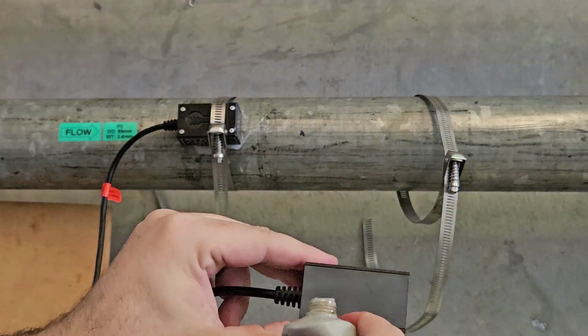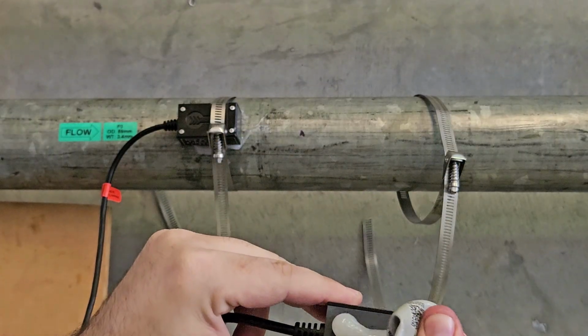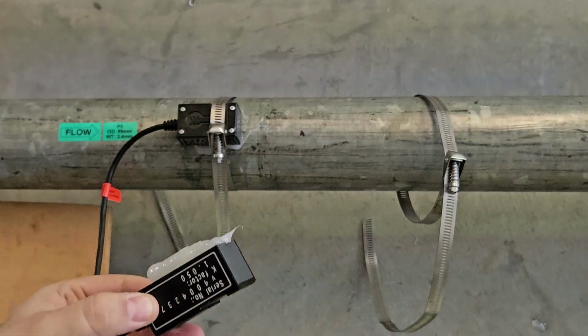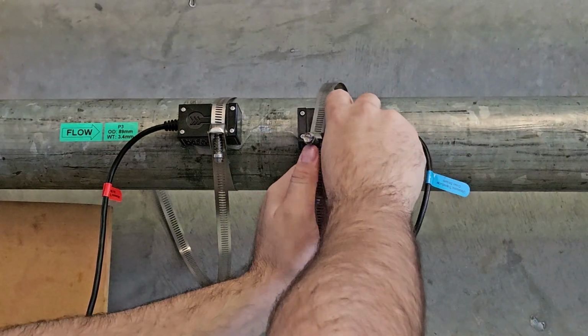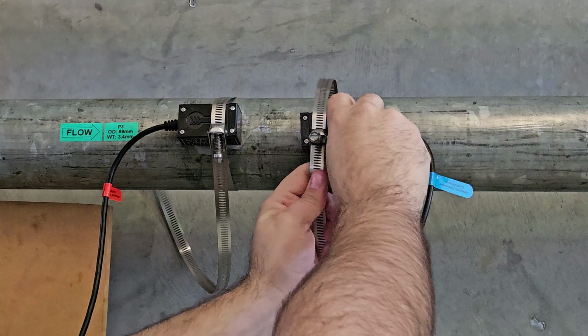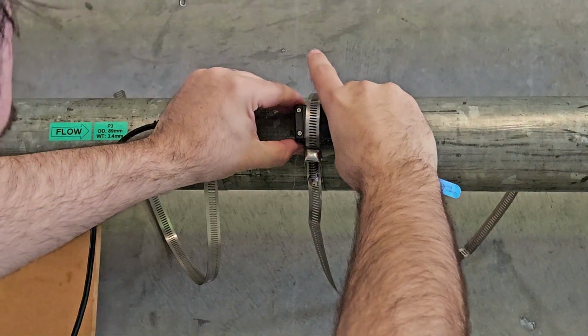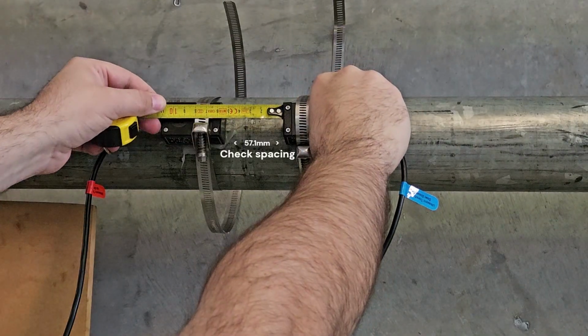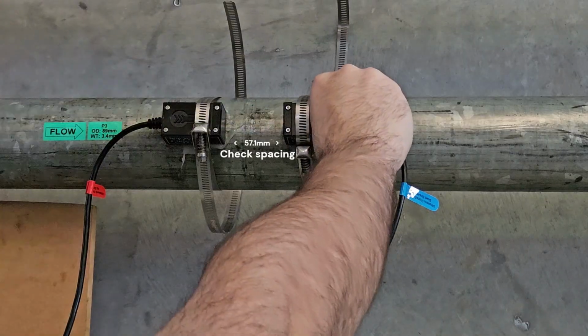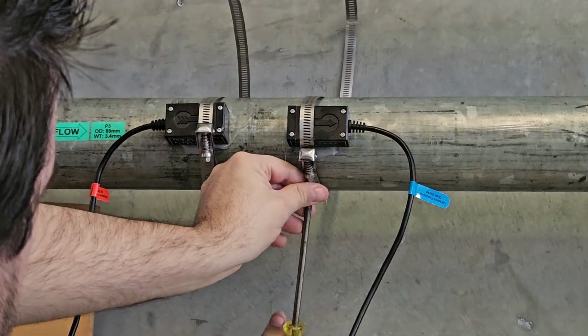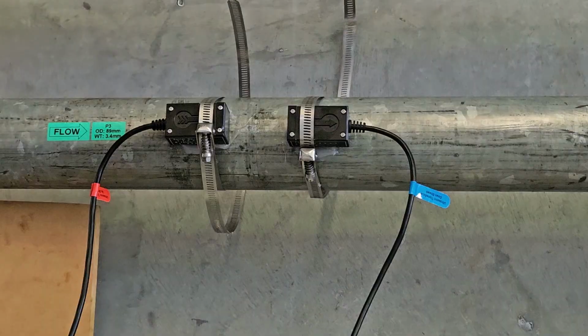Next, take the downstream sensor, checking the label and noting the flow direction. Add couplant and begin spacing the sensor on the pipe, remembering the total space needed between both sensors. Tighten down the pipe straps and start to align the sensors. Using a tape measure, I can make sure the sensors are accurately spaced, matching the required spacing which the meter had displayed. Make fine adjustments until properly spaced and tight.